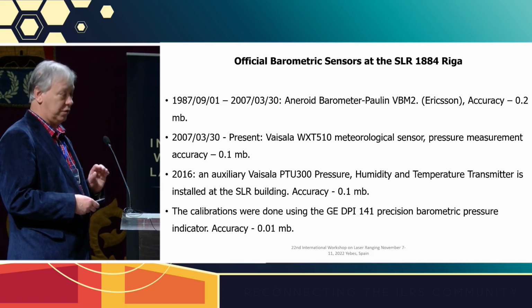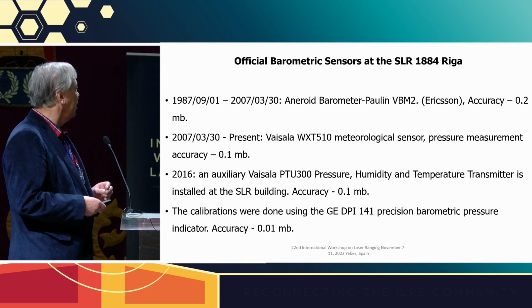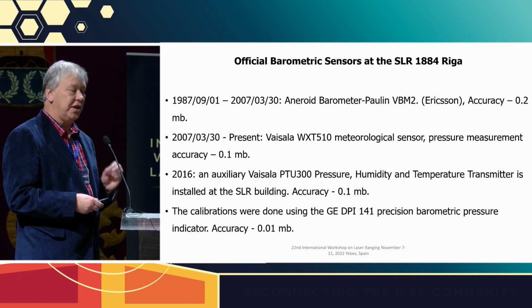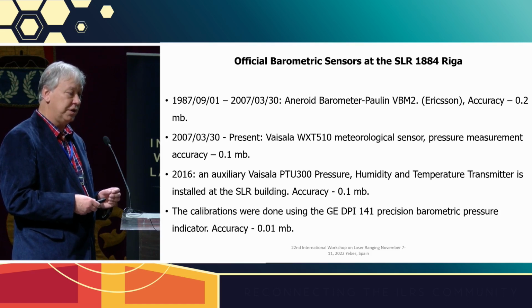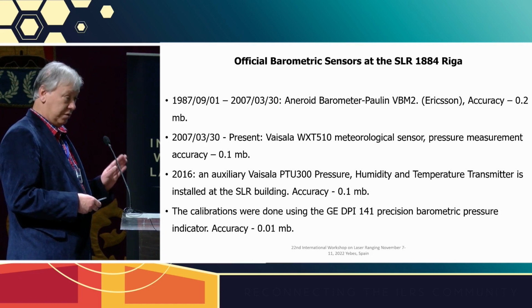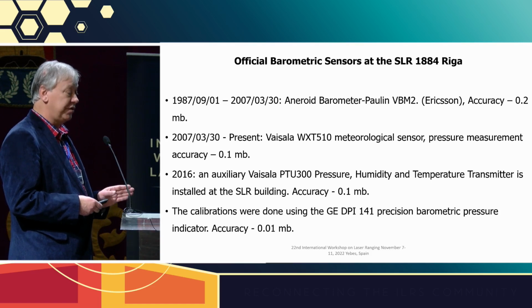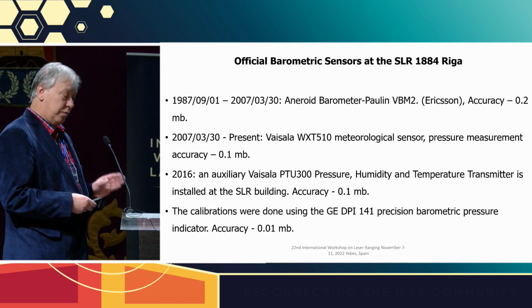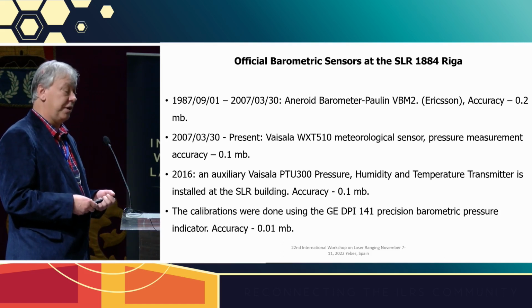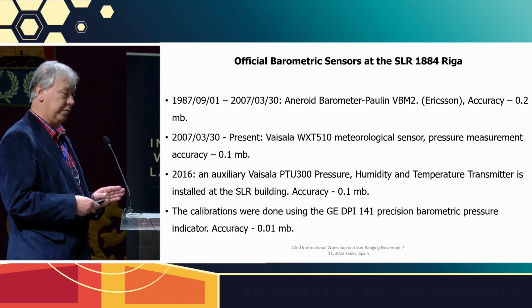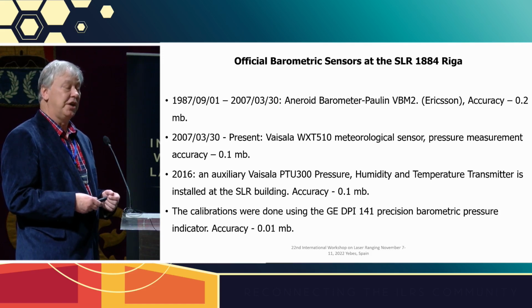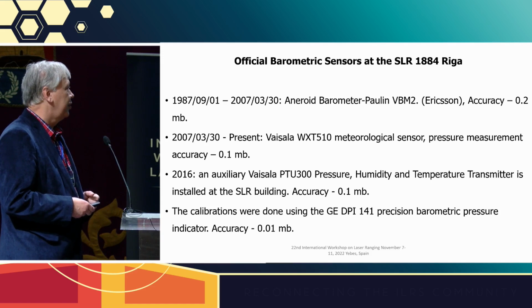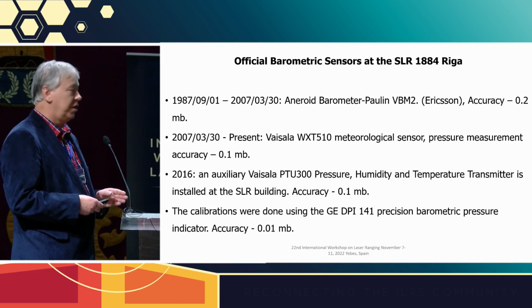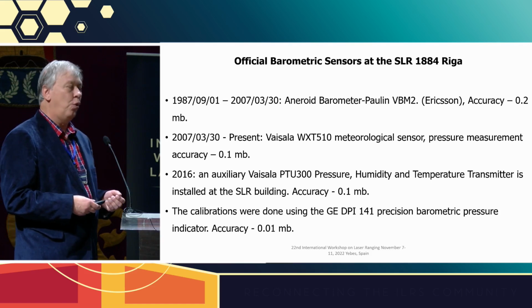This accuracy is valid only for one temperature - our wider temperature range is actually lower, about 0.15. Since 2016 we operate yet another unit, PTU 300, installed as an auxiliary one in the telescope compartment. We tested using a reference pressure sensor for calibration purposes, kindly lent by GFZ Potsdam - the GE DPI 141 model, which has accuracy about 0.01 millibar.